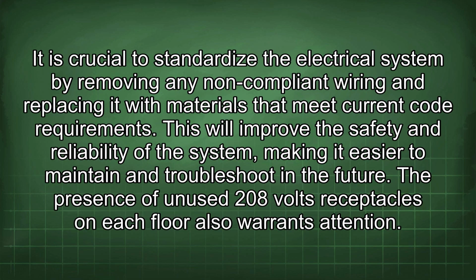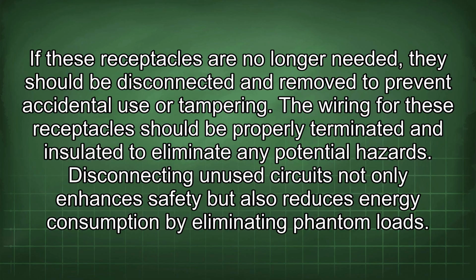It is crucial to standardize the electrical system by removing any non-compliant wiring and replacing it with materials that meet current code requirements. This will improve the safety and reliability of the system, making it easier to maintain and troubleshoot in the future. The presence of unused 208 volts receptacles on each floor also warrants attention. If these receptacles are no longer needed, they should be disconnected and removed to prevent accidental use or tampering. The wiring for these receptacles should be properly terminated and insulated to eliminate any potential hazard.